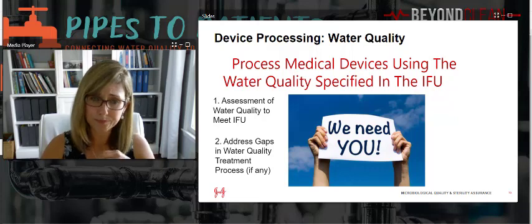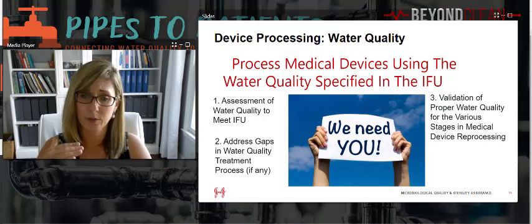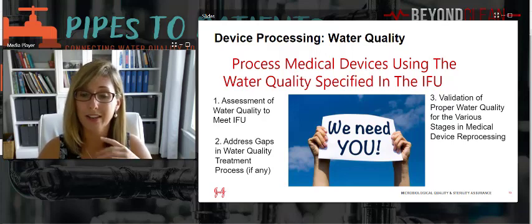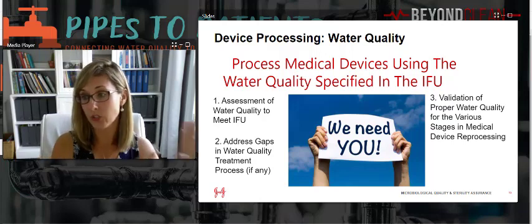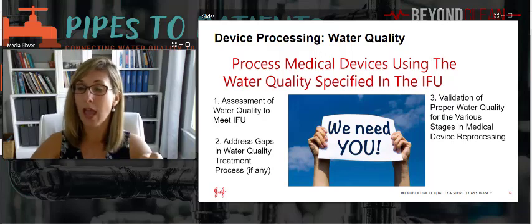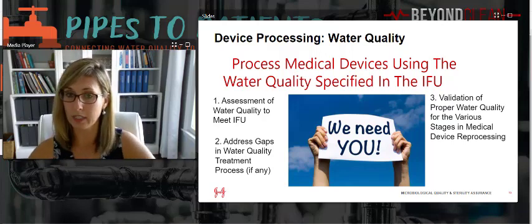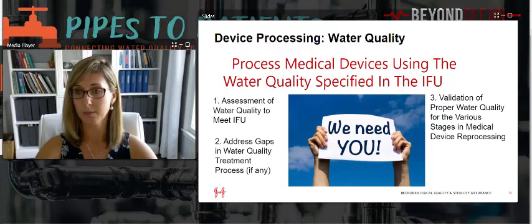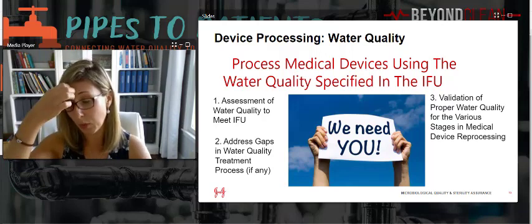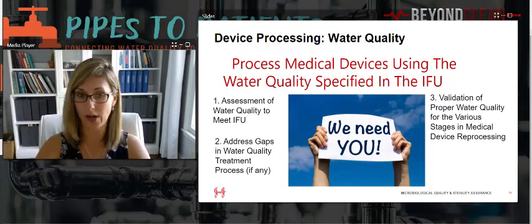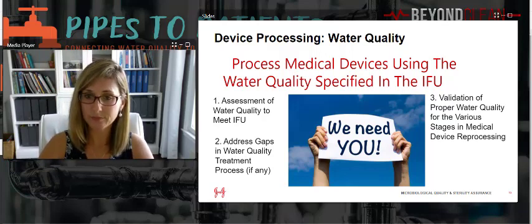And then third, medical device reprocessing areas should be audited to make sure that the water that is in contact with the devices is correct within each area. So it's not just the treatment process, but it's also at what stations the water is being used within sterile processing, making sure that that meets the appropriate level that's required by the IFU for the processing step that's done at that station.